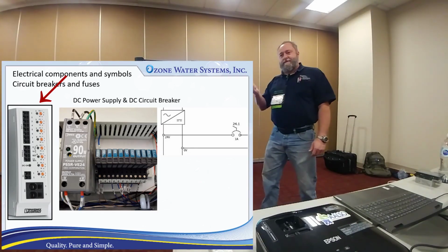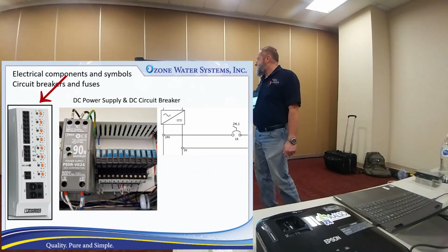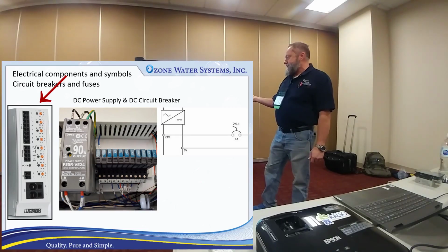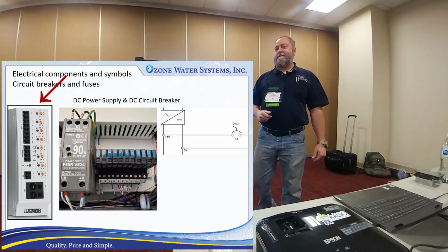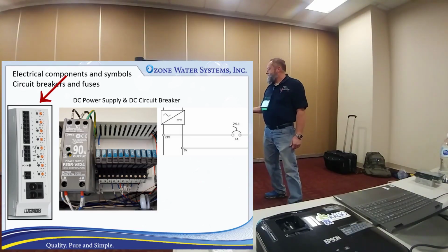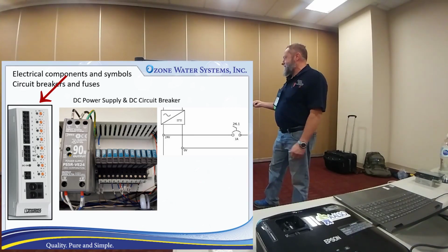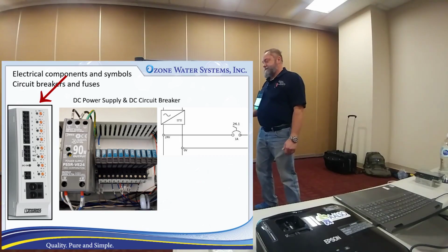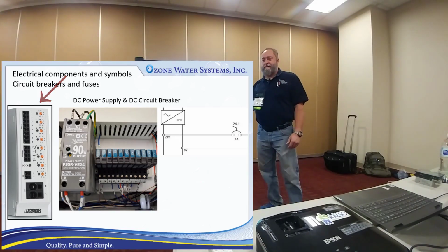Yeah, we've probably got little current transformers in there that monitor current for each branch. They're pretty awesome. And then they've even got status outputs you can send to a PLC or something to give you an indication when you lose a circuit breaker or something, or if there's a fault. So they're pretty nice. I couldn't tell you off the top of my head how they cost compare to just some standard breakers, but we use those as often as we can because they're so valuable for having that information and so easy to readjust.